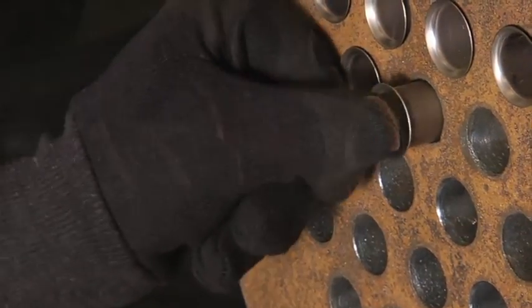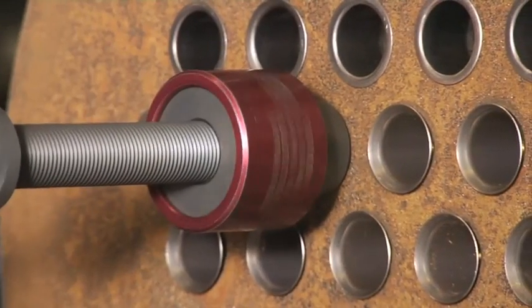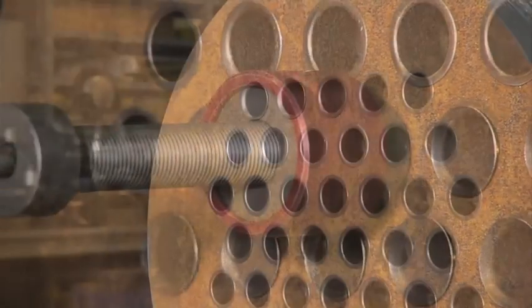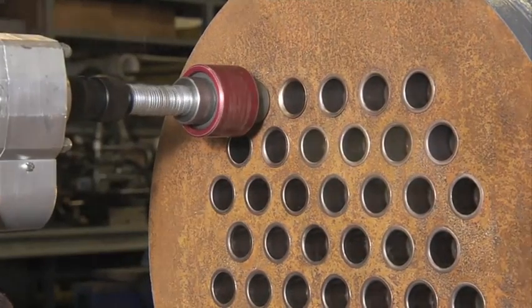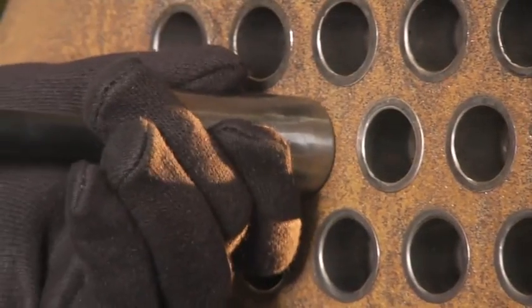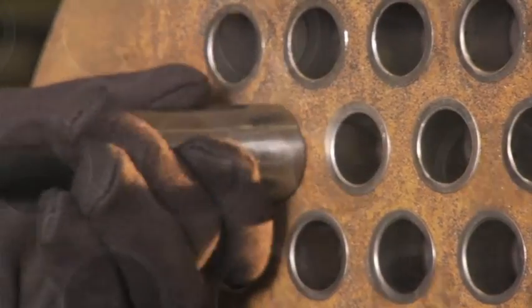The flared end is expanded to a torque setting by use of a conventional tube expander. The downstream expansion is controlled with a mechanical stop. The last step is the final flare of the tubes, so they conform to the tube-to-tube sheet profile.